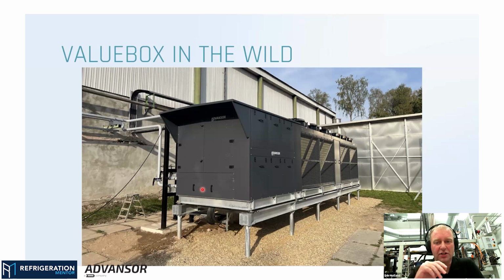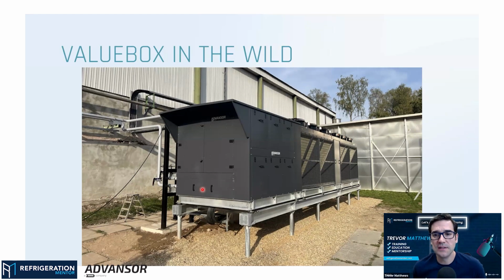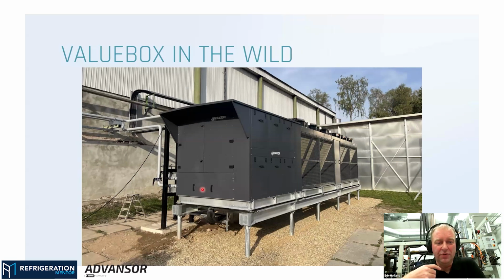Because if you just charge with liquid directly into the system at vacuum, you get dry ice immediately, and it's just a pain to get rid of again. So usually we charge it to something between 7 and 10 bars of vapor pressure. That would be 100 psi-ish of vapor pressure. When that is done, we start filling in liquid.